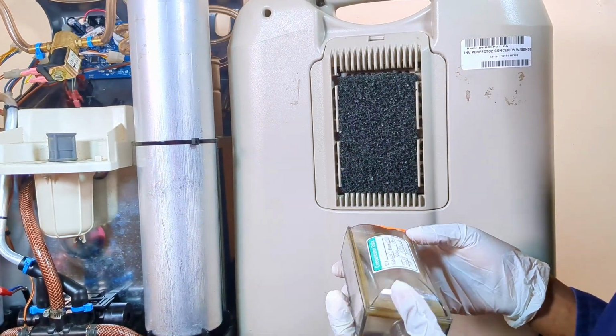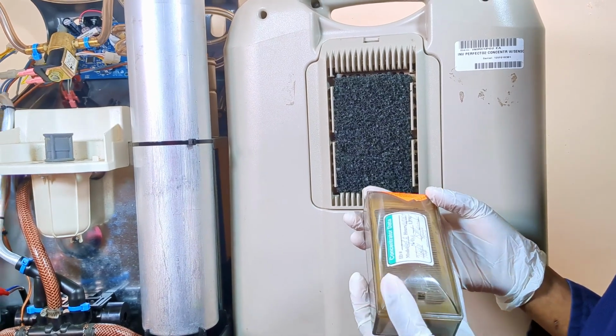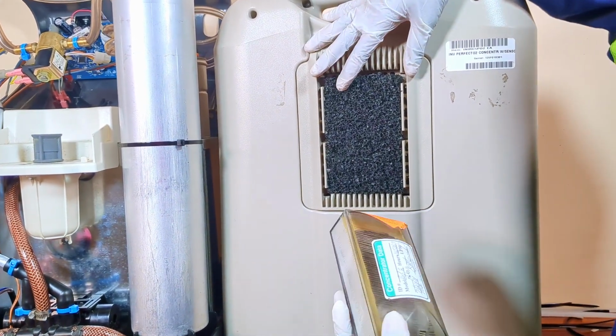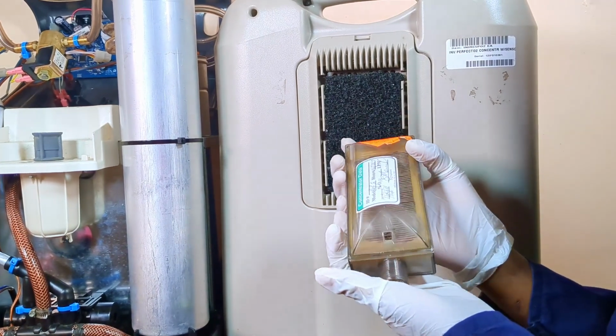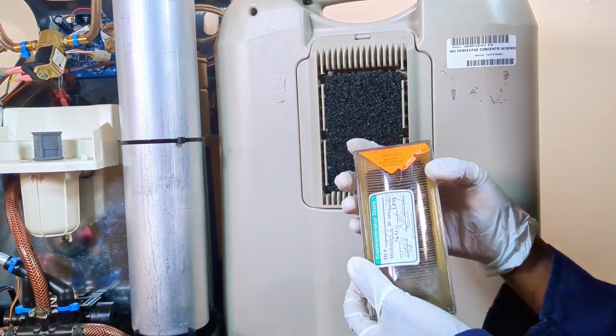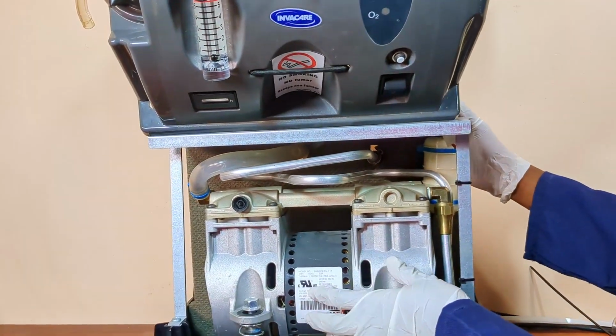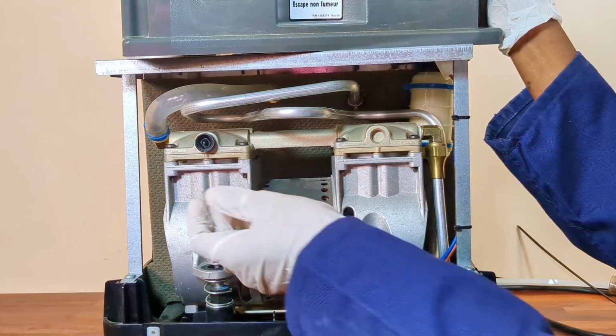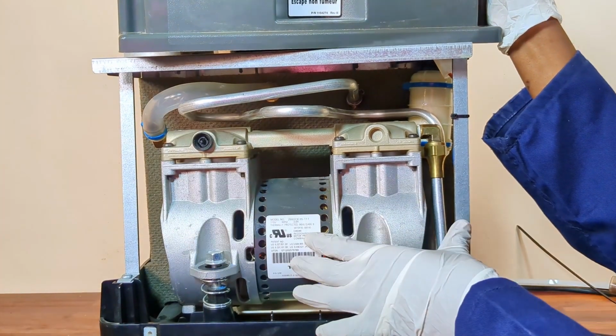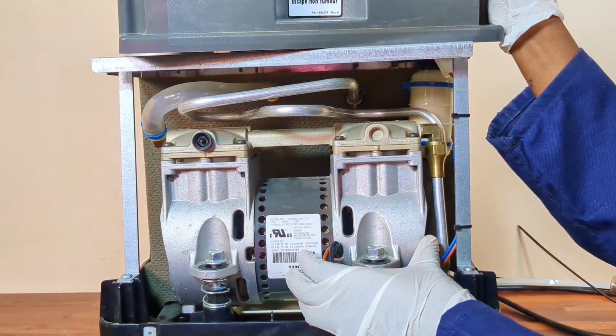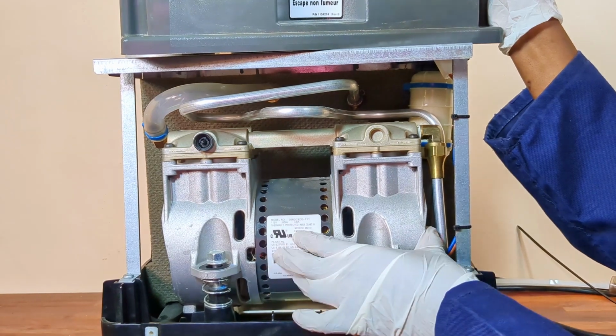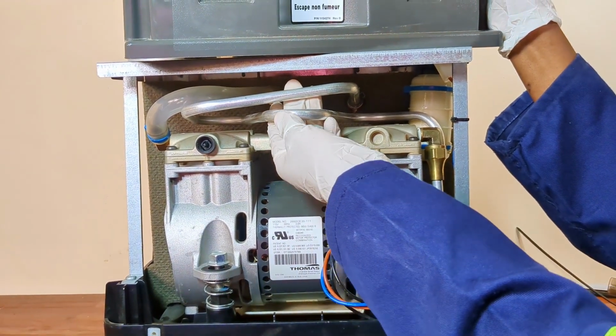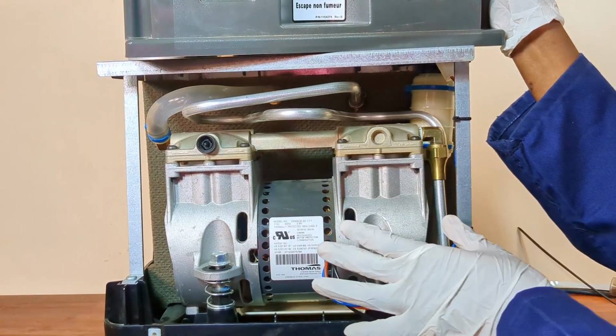I'll now take you through the pneumatic system of the Invacare Perfecto2 Oxygen Concentrator. Firstly, ambient air is put into the machine and it passes through two filters, the cabinet filter and the compressor inlet filter. These filters remove dust and contaminants. The filtered air then enters the compressor through the intake hose. This is where the air is pressurized to a pressure of 21 psi. This compression increases the air temperature, and this is where the heat exchanger comes in order to cool the air before it continues through the system.